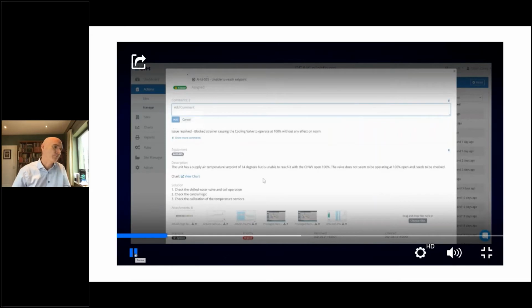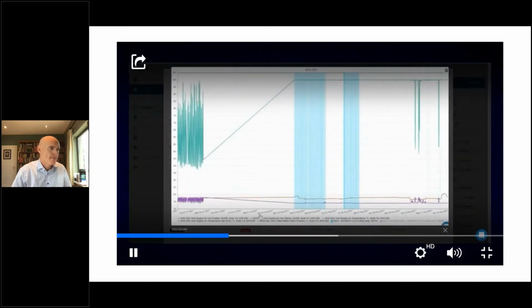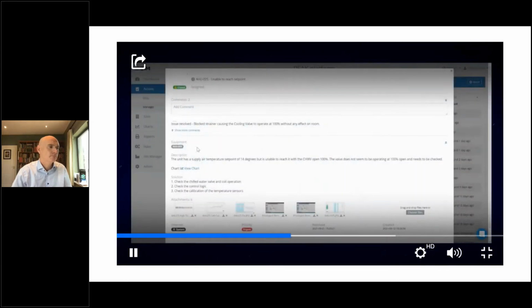So essentially the rules alerted us to an issue where the supply air temperature could not achieve set point, and this air handling unit was feeding a zone that had strict temperature control parameters. What the rules engine picked up was that the chill water valve went to 100% and the supply temperature set point still could not be achieved. As you can see here, the supply temperature was about 4 or 5 degrees above the set point at all times. We raised this with the site team, and the site team reviewed the proposed solution steps put forward by the platform.